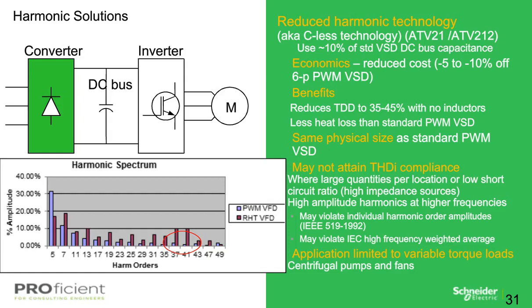Excellent. Here's a question. What about products that suppress harmonics instead of filtering? Harmonic Limited claims that they prevent the third harmonic currents at the source. Okay. Very good lead-in question for my next couple of slides, and we'll get into a pretty detailed discussion on a couple of products that we have for suppression and what some of those technologies do, not only within the 5th and 7th harmonic, but what the effects are of suppressing the 5th and 7th harmonic and increasing, whether it be the 37th or 41st, and really how that looks as a total picture as opposed to just looking at a couple of harmonic orders. So in short, we will discuss that in some detail in the next few slides. Excellent. Thank you, Brian.